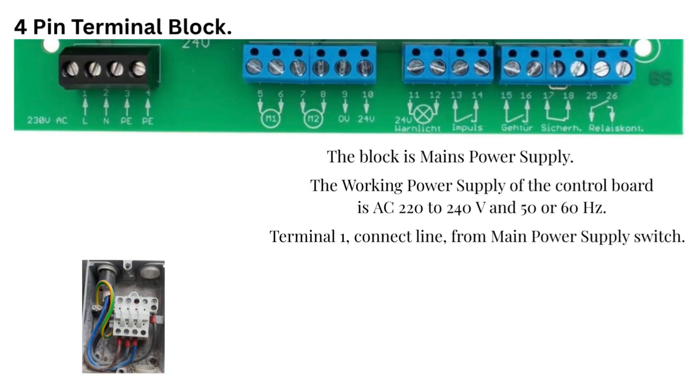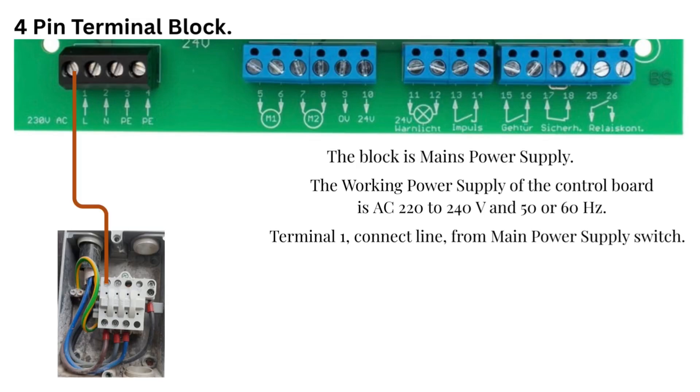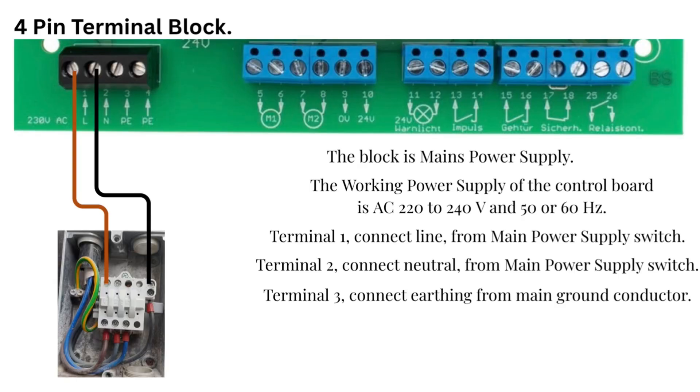Terminal 1 connects line from main power supply switch. Terminal 2 connects neutral from main power supply switch. Terminal 3 connects earthing from main ground conductor. Permissible cable cross-section is 1.5 mm to 2.5 mm square.